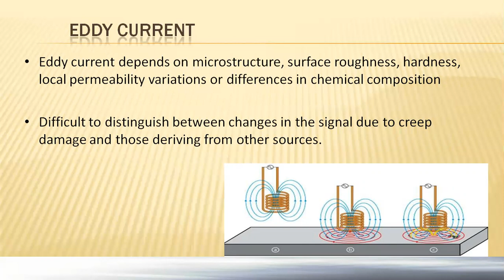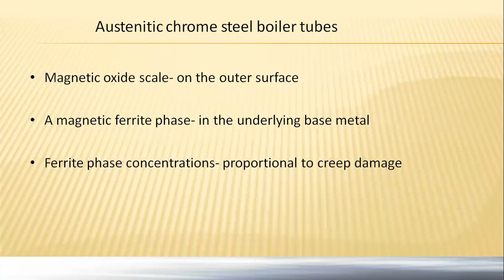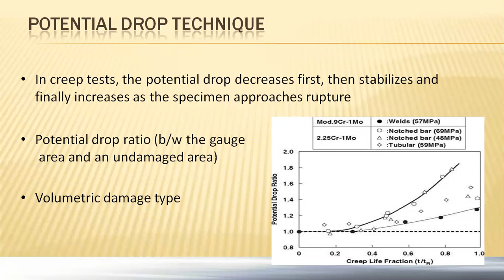And for this, austenitic chrome steel boiler tubes will be utilized for identification and producing of this electromagnetic effect. And the potential drop clearly identifies the areas at which the cracks have been identified. Gradually, in the creep test, the potential drops will decrease initially, and later on it will stabilize. And finally, it will increase slightly upon its variational levels. And later on, we can confirm the volumetric damage. So volumetric in the sense how much dimensions, size, depth, length, and its three-dimensional ratios can be clearly examined. So hence volumetric damages can be identified.